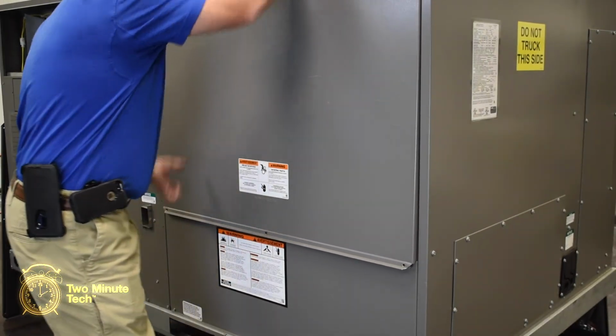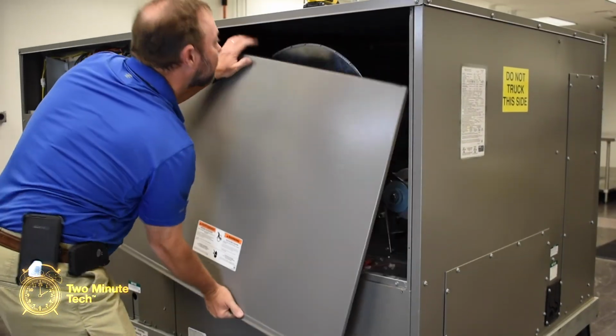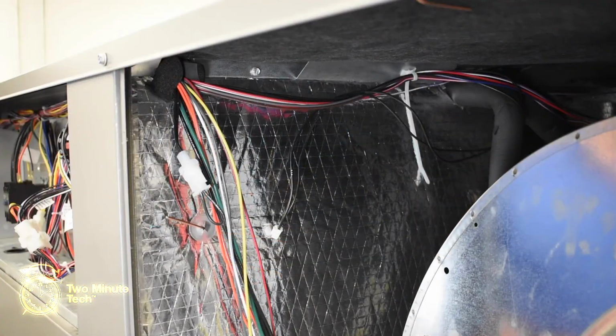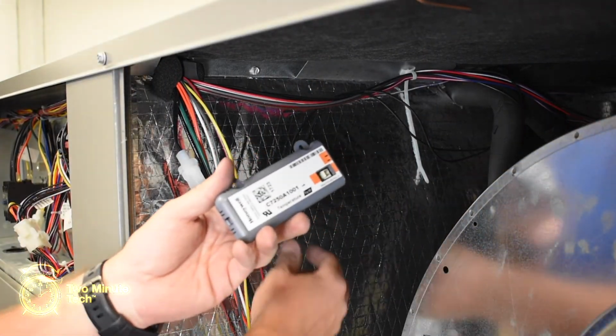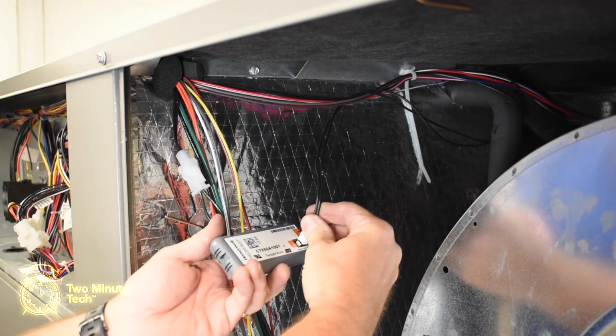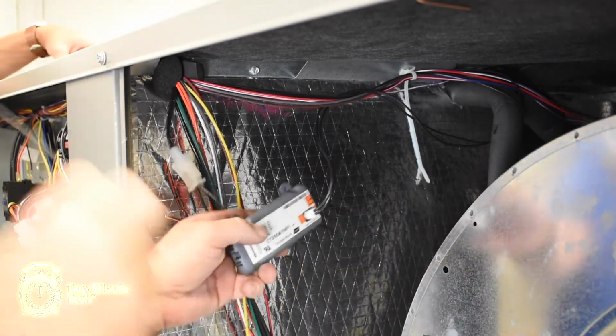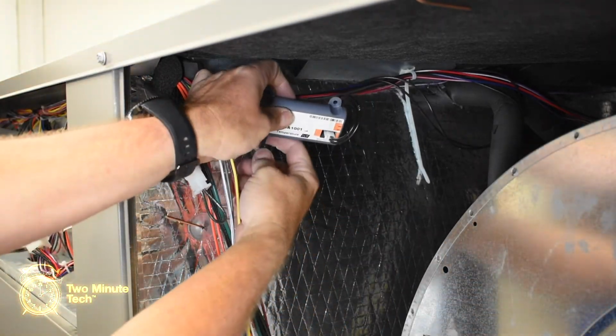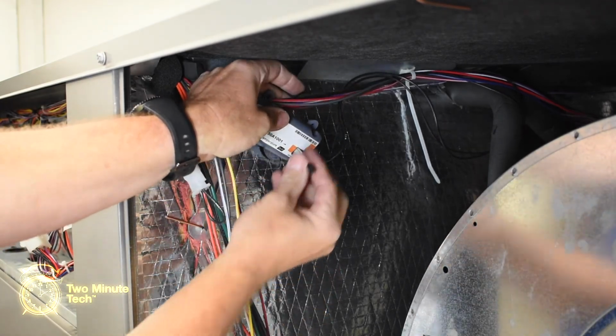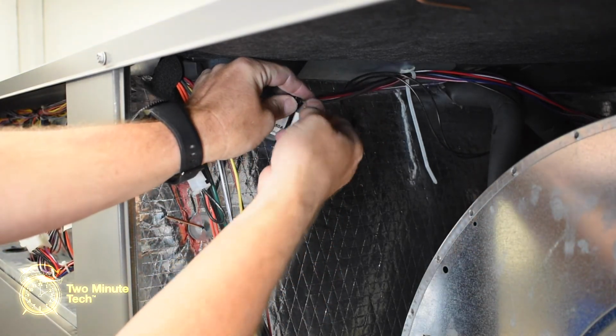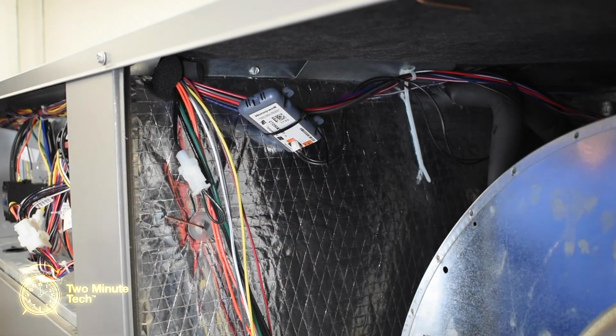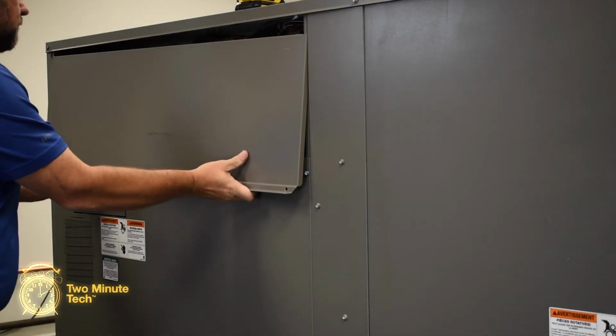Remove the blower access cover so the mixed air temperature sensor, with the orange markings on the label, can be installed. On the wiring harness near the top left-hand side of the blower compartment, locate the free 2-pin white Molex connector with black wires. Plug this connector into the temperature sensor and secure the temperature sensor to the wiring harness using a cable tie. Remove the control panel access cover.